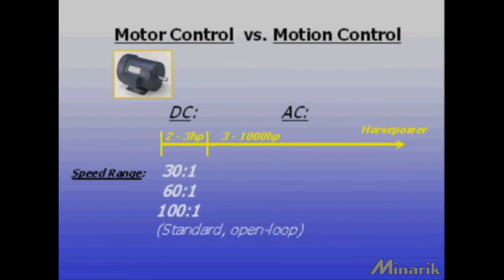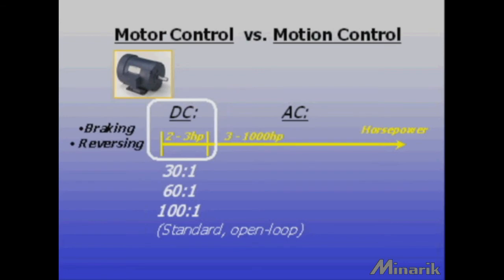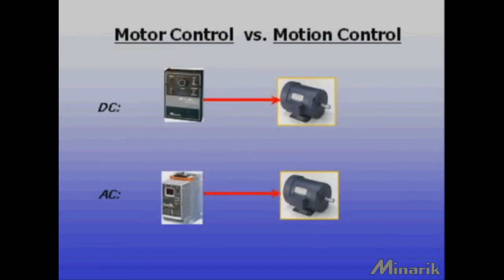Above 3 horsepower, DC motor cost increases quickly, but superior open loop speed range, braking, and reversing makes DC a good choice for small horsepower variable speed applications. AC or DC performance can also be improved by using higher cost drives and feedback devices.